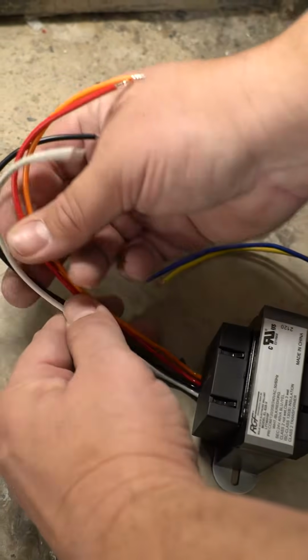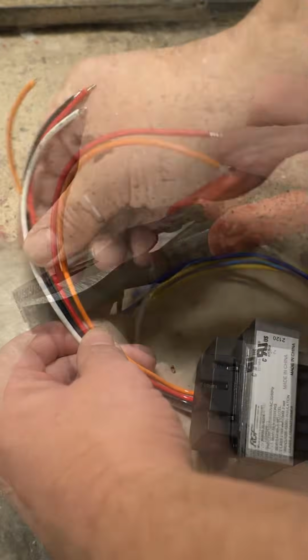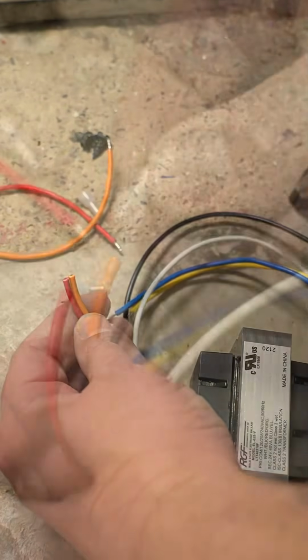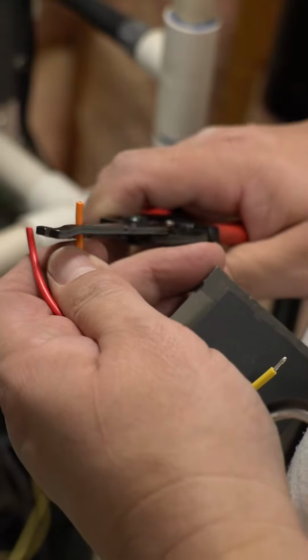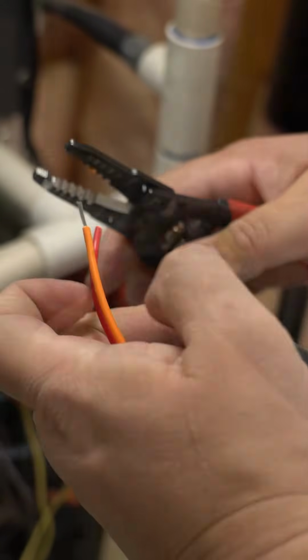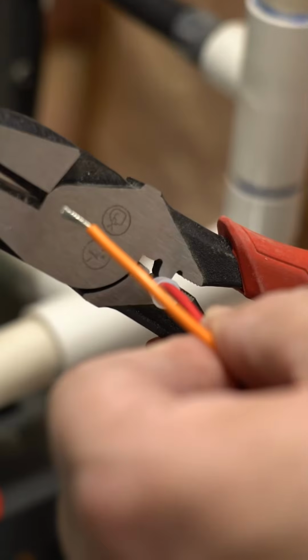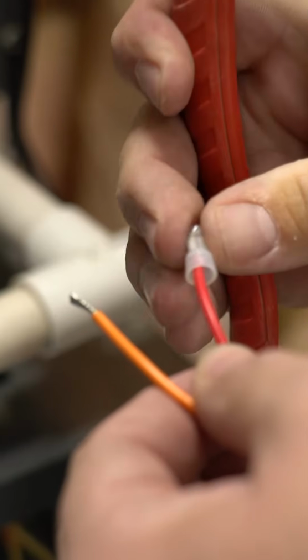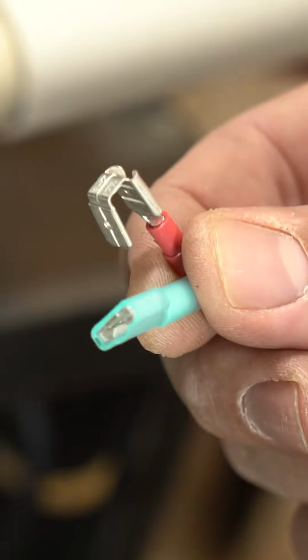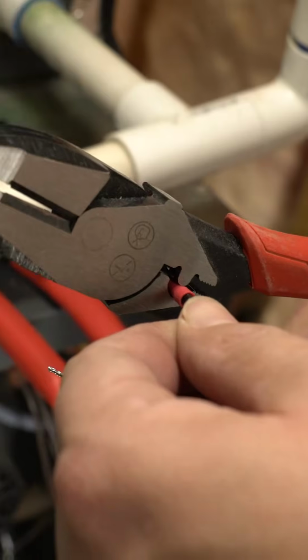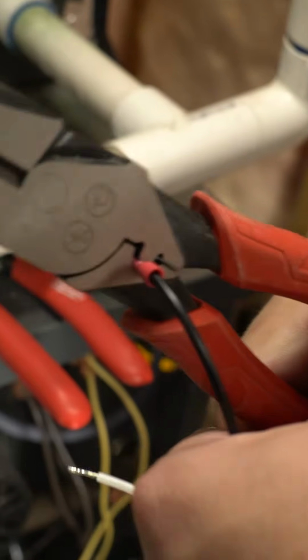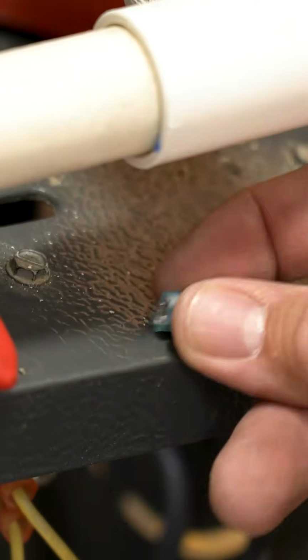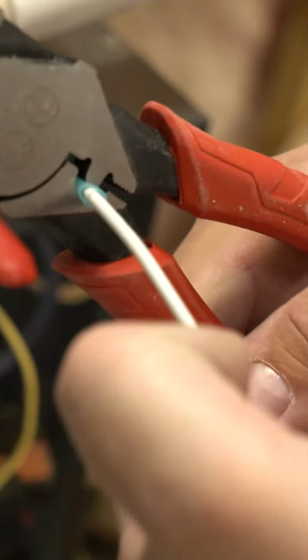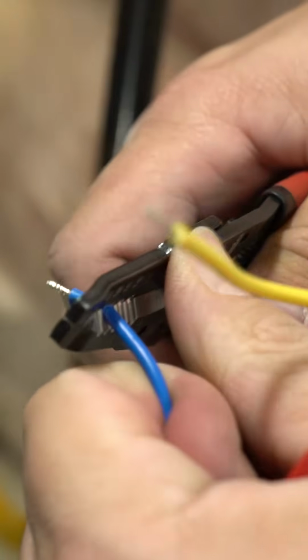I find it easier to prepare my connections before I mount the transformer. I'm going to trim and cap off the wires I'm not going to be using. You may need to strip your wires depending on the size of your wire end caps. I'm just going to use my lineman pliers to crimp the end caps onto the red and orange wires. I'm going to put a quick splice spade connector on the black wire and a female spade connector on the white wire. Use your pliers again to crimp the connectors onto the wires. Next, strip the yellow and blue wires.